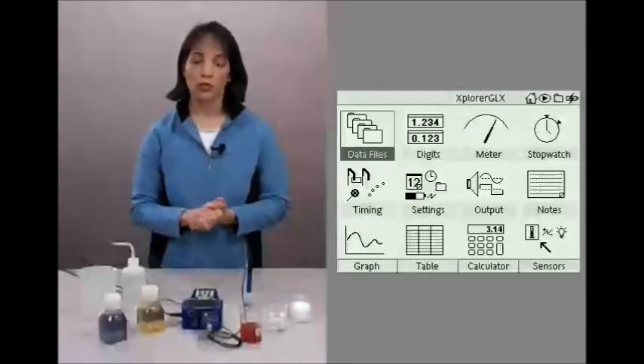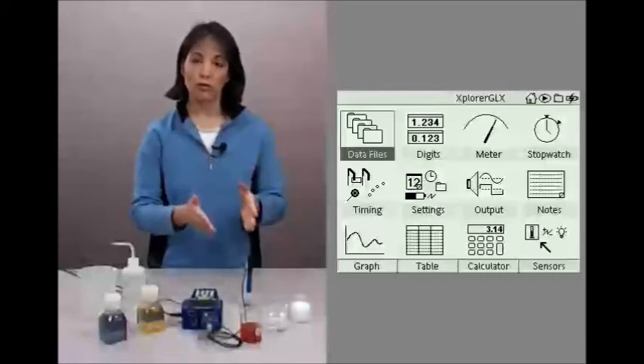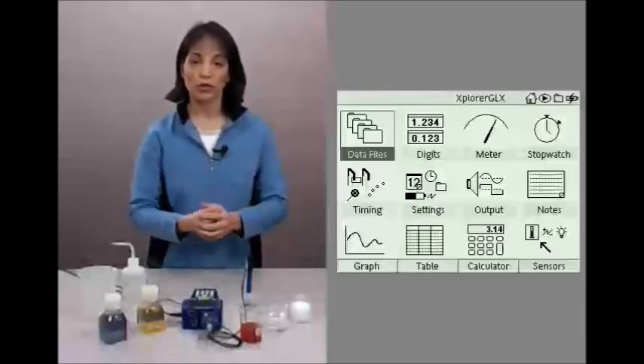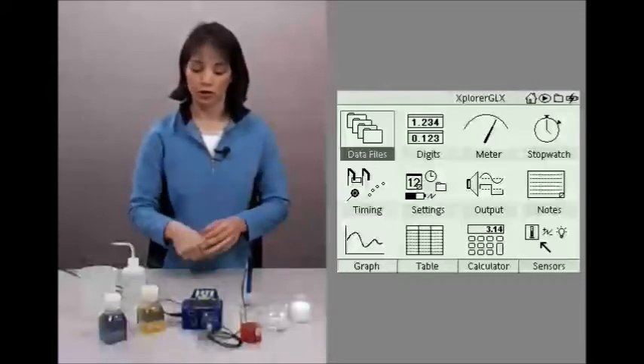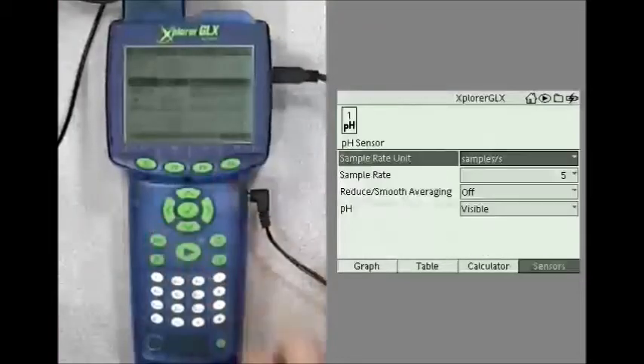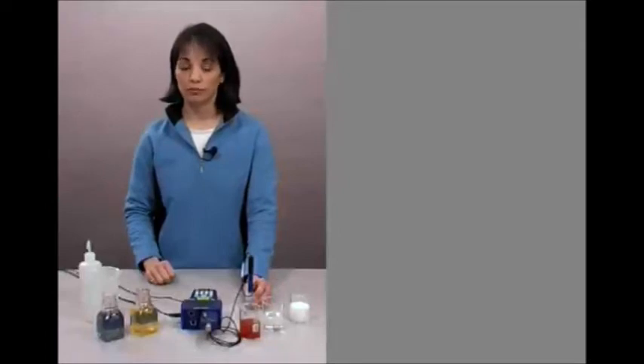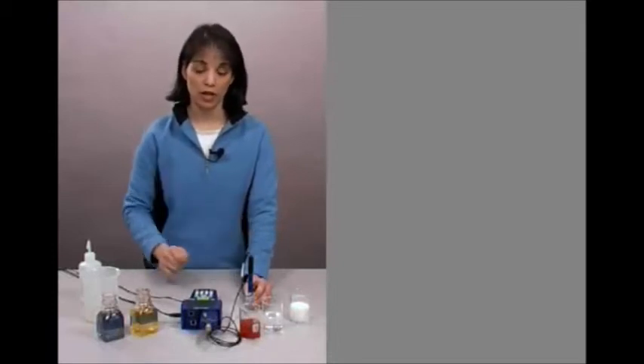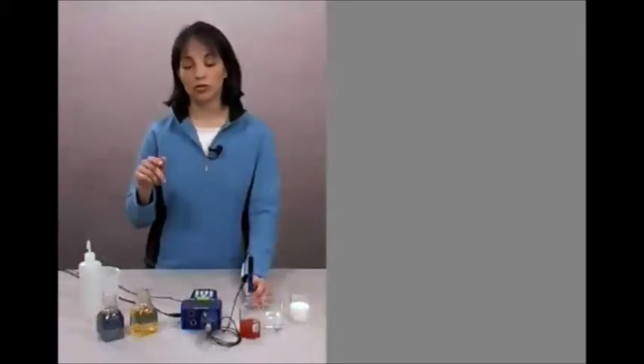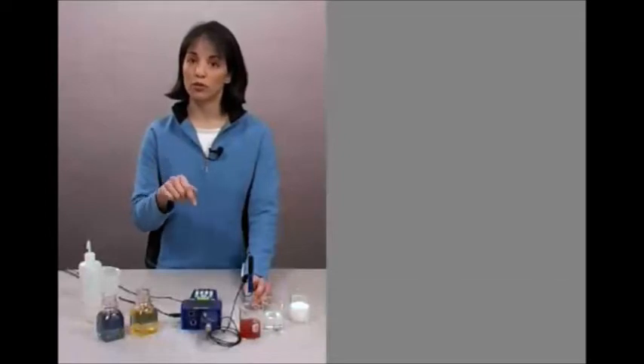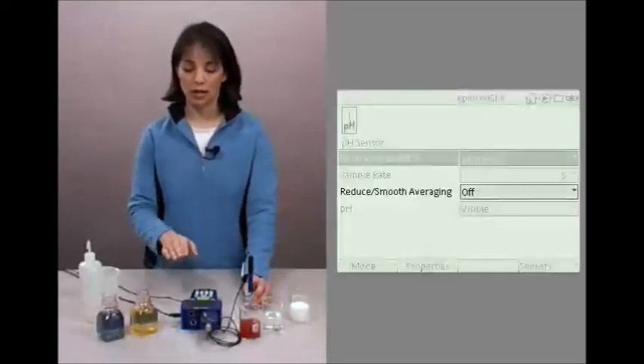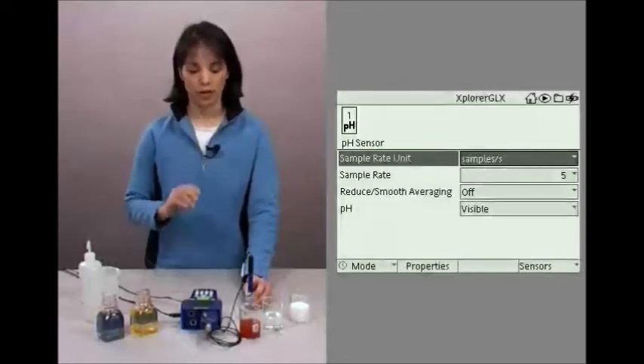Okay, because what we want to do is a number of things with the sensor, we are going to go to our sensor screen. So that you can do by pushing the F4 button. There are 3 things we need to do in this screen. First, calibrate the sensor. Second, set it up for manual sampling. And finally, we are going to show you how to use that reduce/smooth averaging field in this screen here.